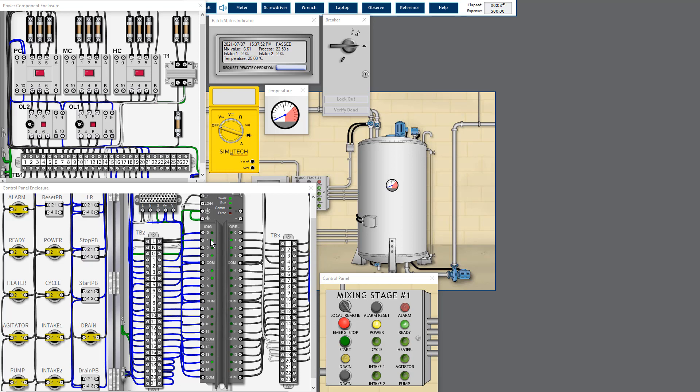Usually the PLC input channel LED status for channel 1, 3, 4, 5, and 14 turns on under normal condition. Whereas for the PLC output channel LED, LED number one and two are supposed to be turned on as per the drawing.